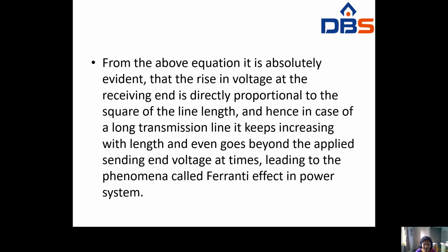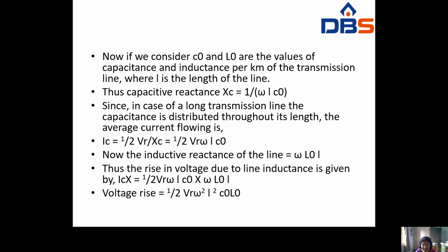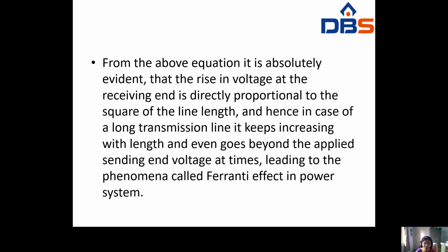Hence in case of a long transmission line, as the length keeps increasing, the receiving end voltage can even go beyond the applied sending end voltage, leading to the phenomenon called the Ferranti effect in power systems. So whenever the length increases, the voltage rise will increase, and at that time it may cause the Ferranti effect. That's why, from this equation, you can say that the Ferranti effect occurs only in long transmission lines.